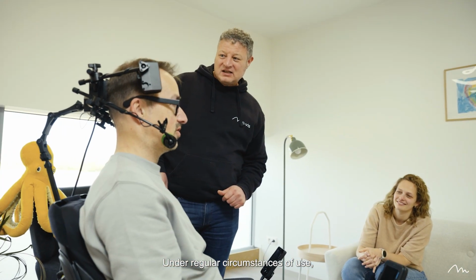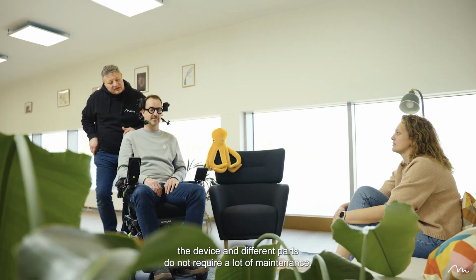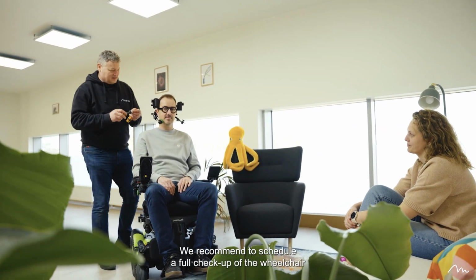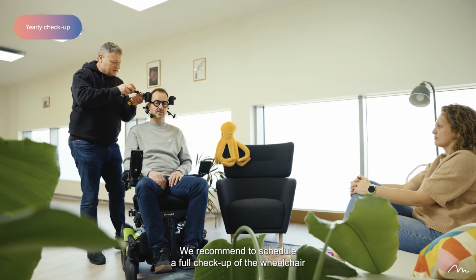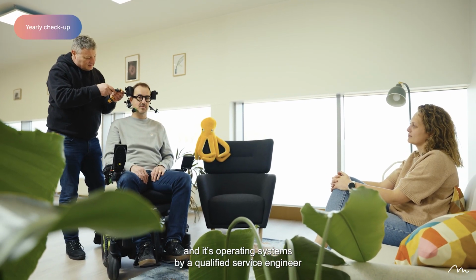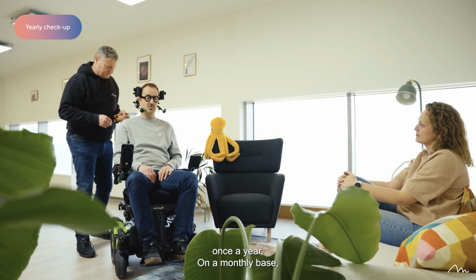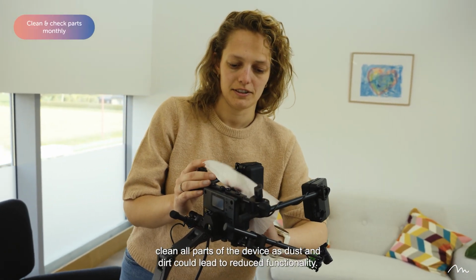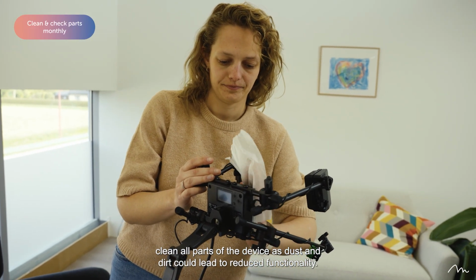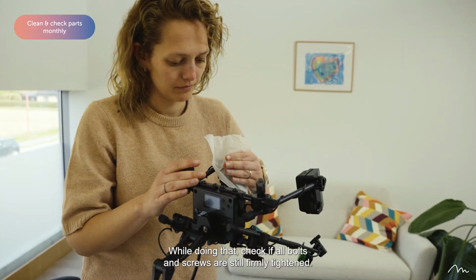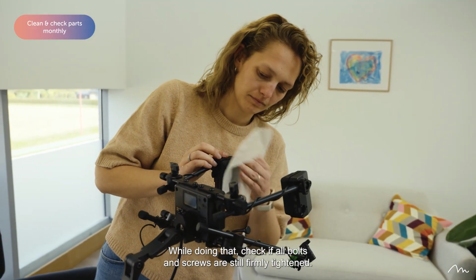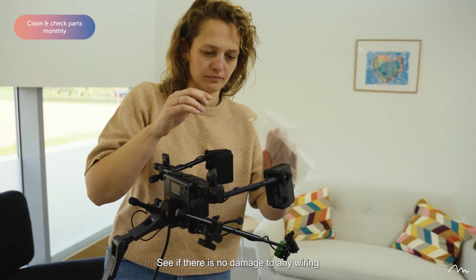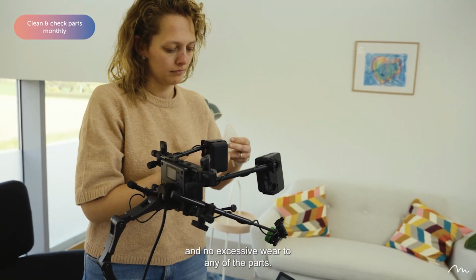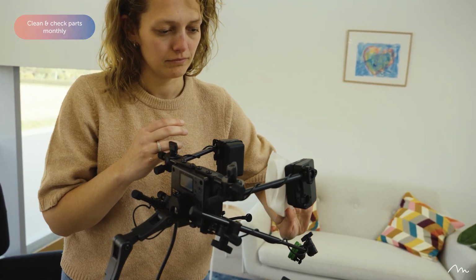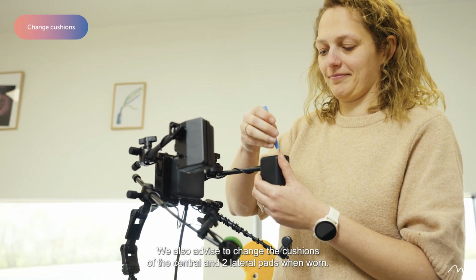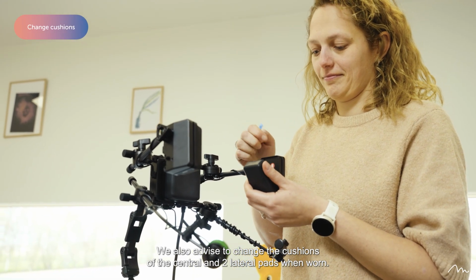Under regular circumstances of use, the device and different parts do not require a lot of maintenance. We recommend to schedule a full checkup of the wheelchair and its operating systems by a qualified service engineer once a year. On a monthly basis, clean all parts of the device as dust and dirt could lead to reduced functionality. While doing that, check if all bolts and screws are still firmly tightened. See if there is no damage to any wiring and no excessive wear to any of the parts. We also advise to change the cushions of the central and 2 lateral pads when worn.